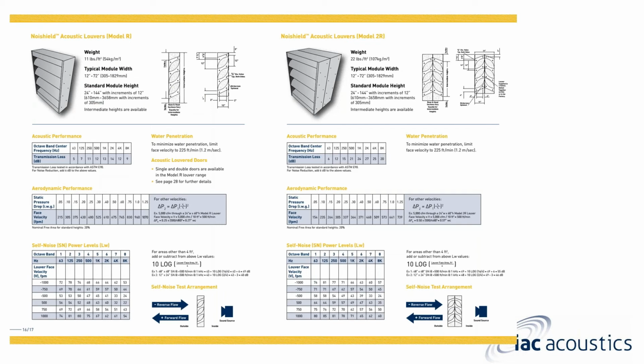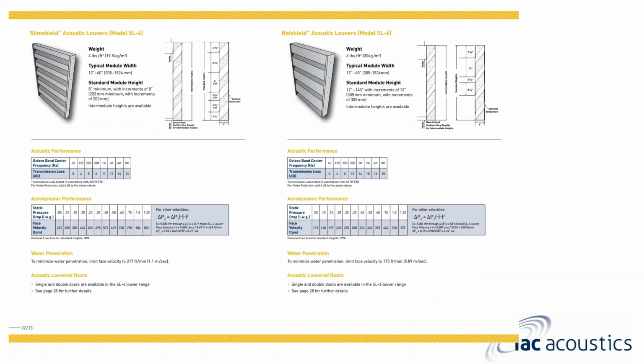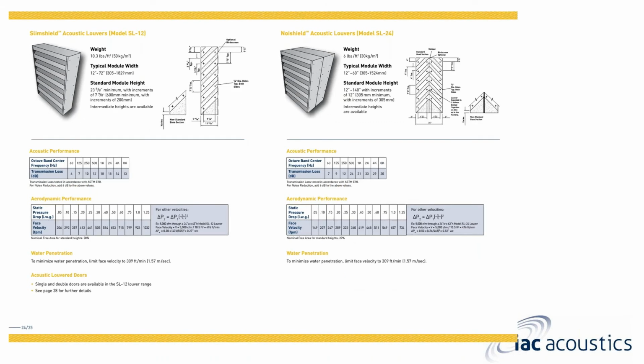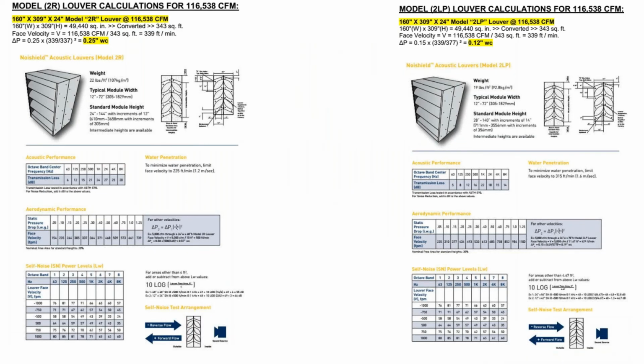Breaking it down, we have our Model R and 2R. The 2R is now a chevron look, 24 inches in depth. Same thing with our LP and 2LP. We have our SL4 at 4 inches in depth and SL6, 6 inches in depth. We also then have our SL12 and SL24. These are straight instead of the airfoil. And here's a nice little comparison between our Model 2R and 2LP. Same characteristics, same width by height, depth, same CFM. You can see with the Model 2R, that 0.25 water gauge, and the Model 2LP at 0.12.